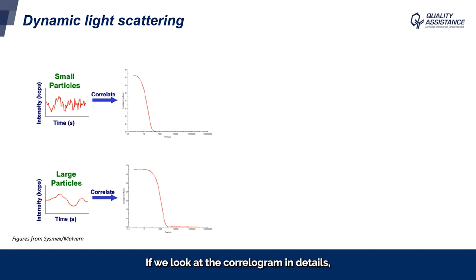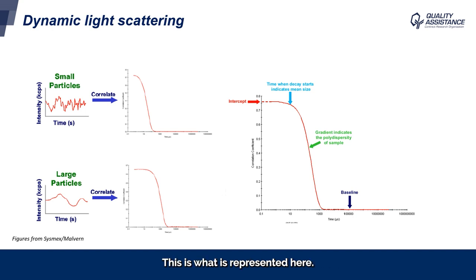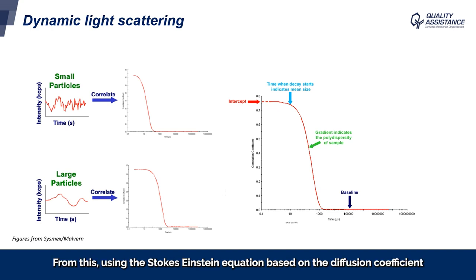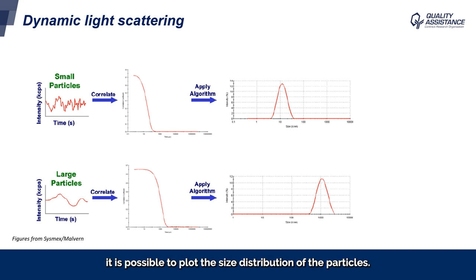If we look at a correlogram in detail, the first part is the decay, which is the indication of the size. So for a small particle, the decay is faster than for a large one. The second part, the slope, is an indication of the polydispersity, and the signal goes back to a baseline. From this, using the Stokes-Einstein equation based on the diffusion coefficient, it is possible to plot the size distribution of the particles.